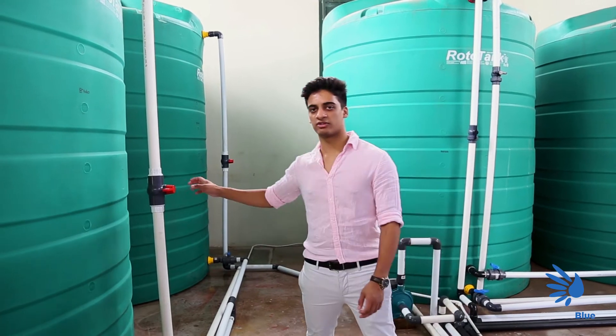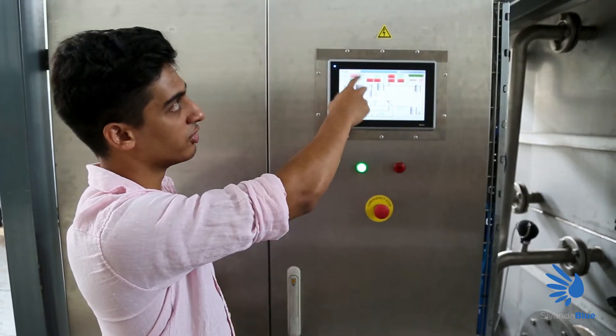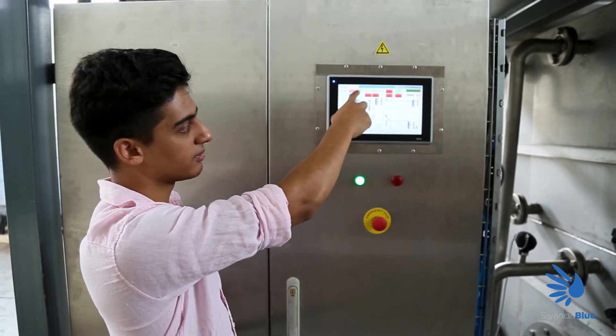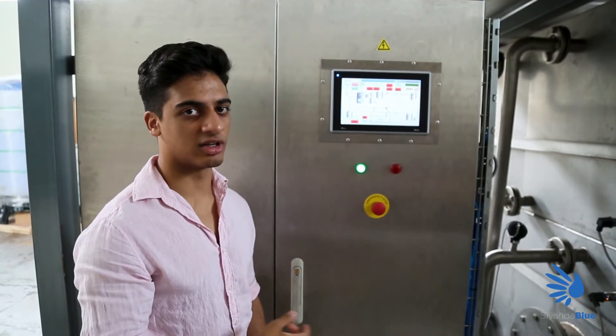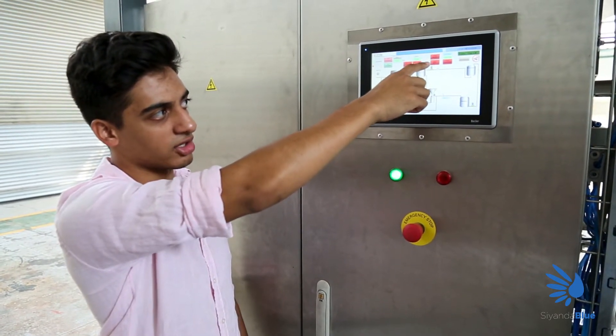We then ensure that the valves on the inlets of the AdBlue storage tanks are open. The next step involves the control panel. You're going to enter the amount of urea added to the hopper here in weight. Once that is done, the system will automatically calculate the amount of water needed to mix with the urea. From there we will then start the blender and start the pump.